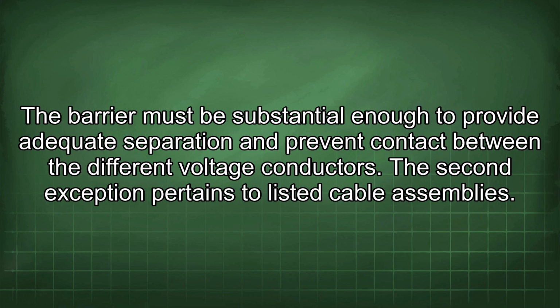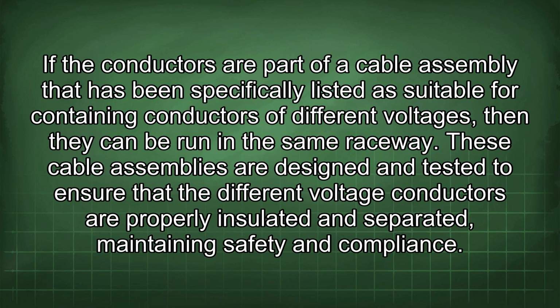The second exception pertains to listed cable assemblies. If the conductors are part of a cable assembly that has been specifically listed as suitable for containing conductors of different voltages, then they can be run in the same raceway. These cable assemblies are designed and tested to ensure that the different voltage conductors are properly insulated and separated, maintaining safety and compliance.